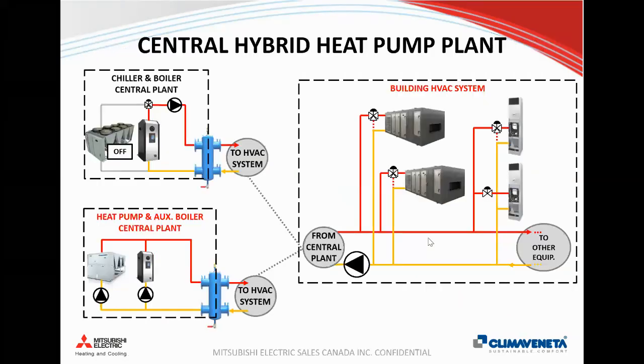So typically in buildings, in the example specifically for a 2-pipe system, typically those systems will have a chiller to use in the summer and a boiler to use in the wintertime. So typically in a 2-pipe changeover system, you're either supplying hot water or chilled water at any given time to all the equipment within the building that's supposed to heat or cool the spaces. So for example, this example shows some air handlers and fan coil units operating in heating mode.